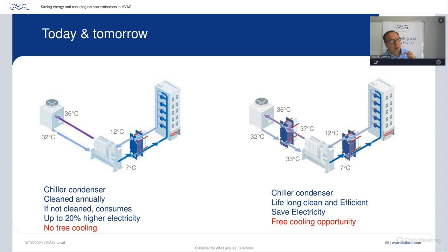Now, what's happening? We find a lot of chillers that are working with water-cooled condensers, and the condenser of the chiller is receiving cooling tower water, let's say at 32 degrees Celsius, and returning back at 36. And the cooling tower water is used to condense the gas. Now, the problem with this, I will show you a little later as well, is that the chiller condenser has to be cleaned annually because calcium carbonate or scale in the cooling tower water actually cooks inside the condenser tubes.